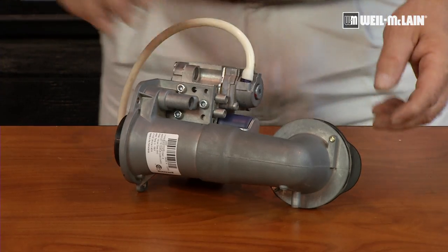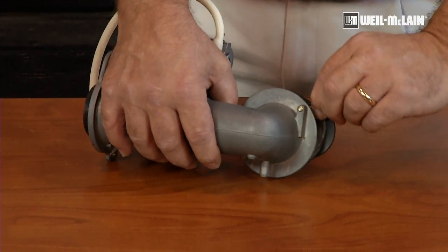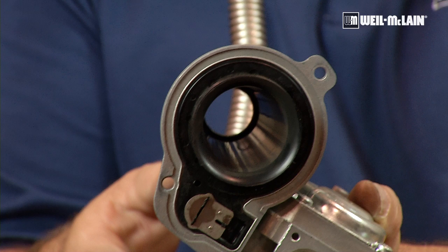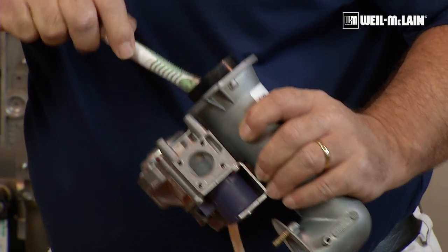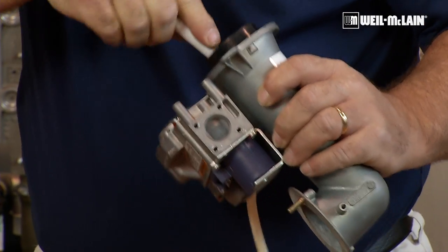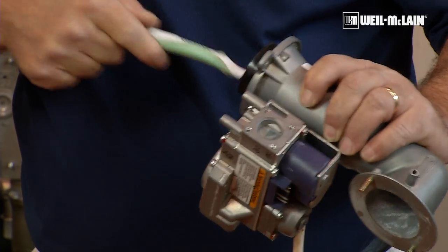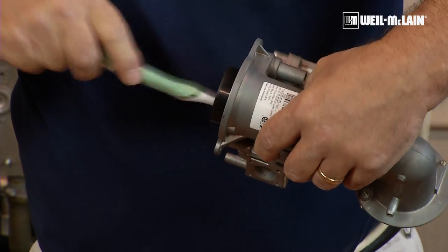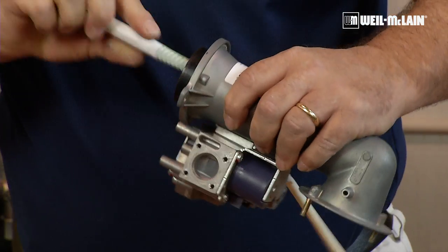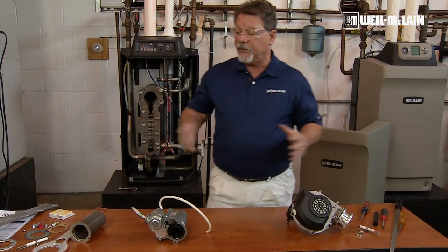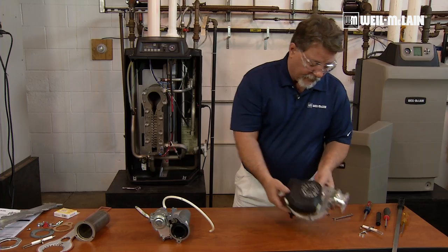The next component that I have here is the gas valve venturi assembly. And obviously we're going to remove and replace the gasket that's on there. We're going to take our venturi cleaning brush and make sure that I get in there and remove any soot, any ash deposits, any debris from the inside of that venturi. So after we've taken that off and cleaned the venturi out, we're really ready to reassemble the components here.